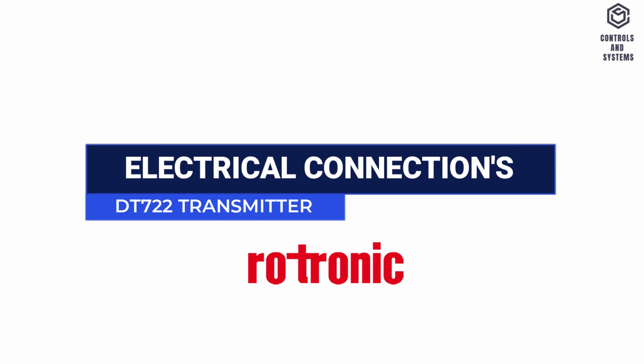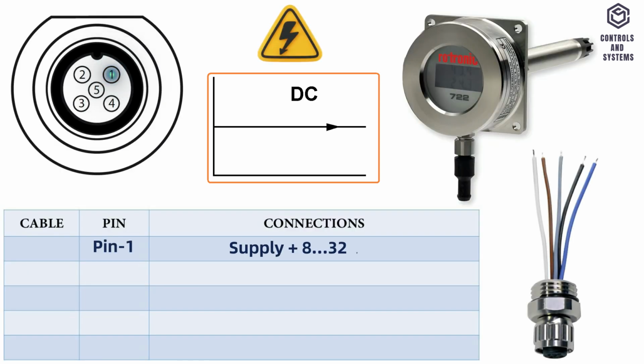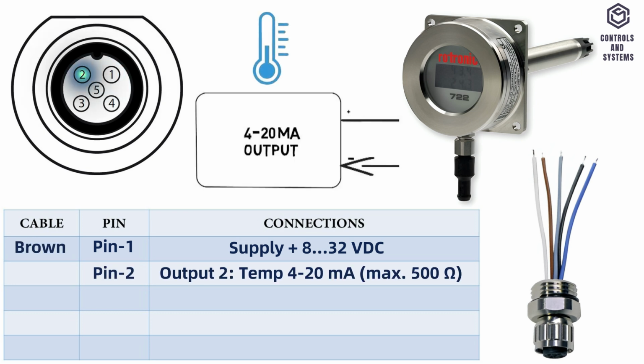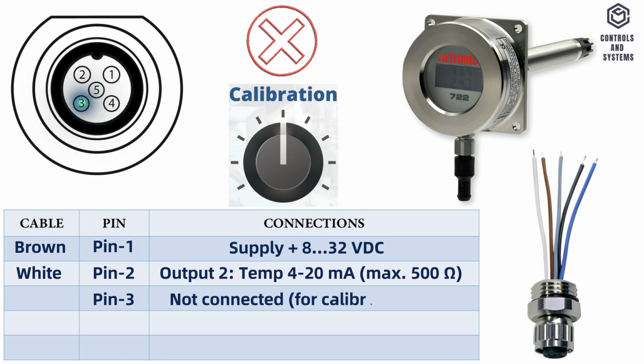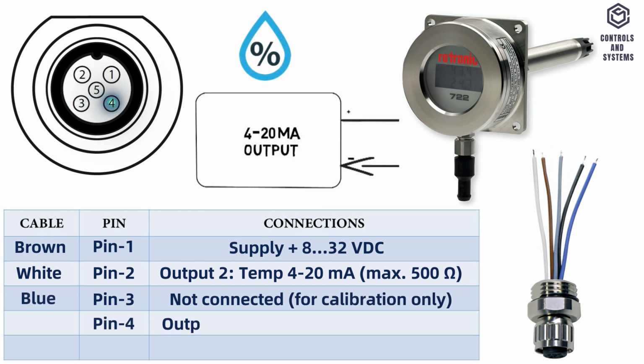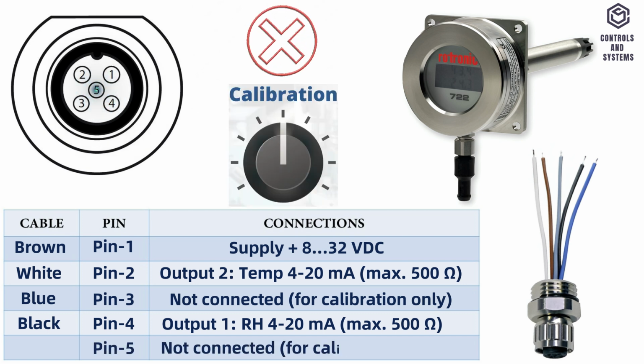Electrical connections: pin 1 is the sensor power supply, 8 to 32 volt DC, and the cable is brown. Pin 2 is the output 2, for 4 to 20 mA temperature signal, and the cable is white. Pin 3 is not connected, for calibration only, and the cable is blue. Pin 4 is the output 1, for 4 to 20 mA humidity signal, and the cable is black. Pin 5 is not connected, for calibration only.